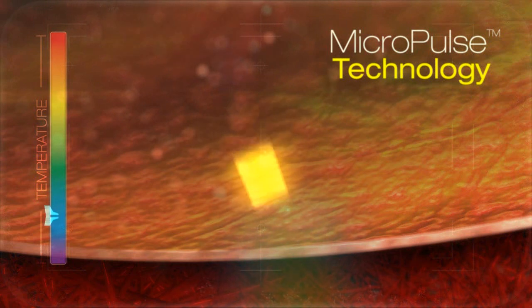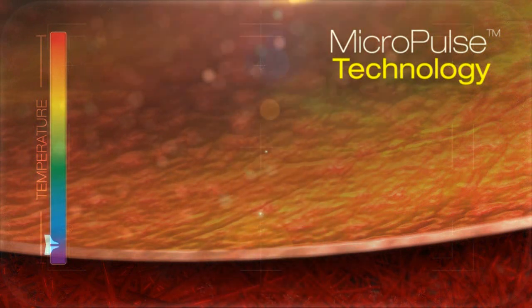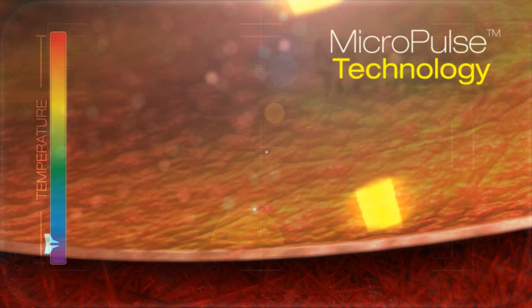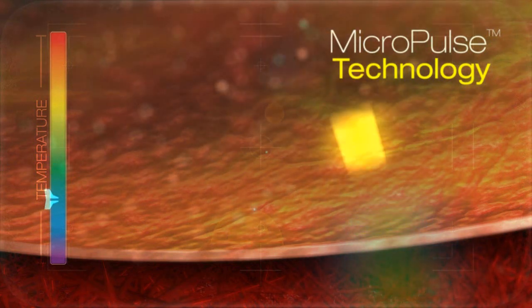Repeating this pulse train can limit the overall thermal spread to the adjacent tissue. This tissue-sparing modality allows physicians to perform therapeutically effective treatments without the coagulation seen with conventional CW laser therapy.